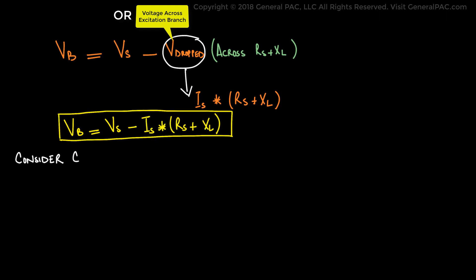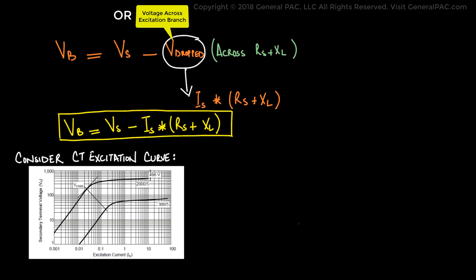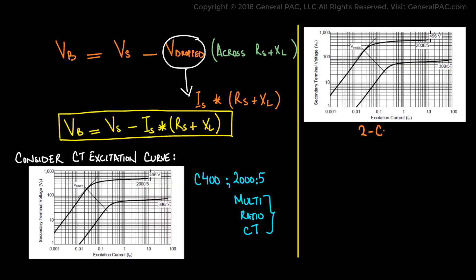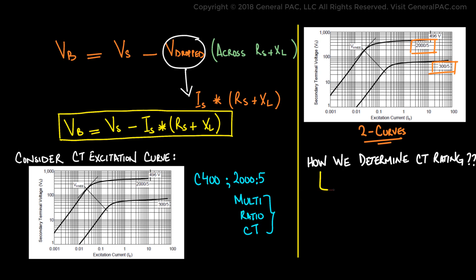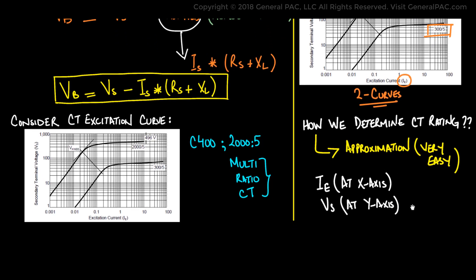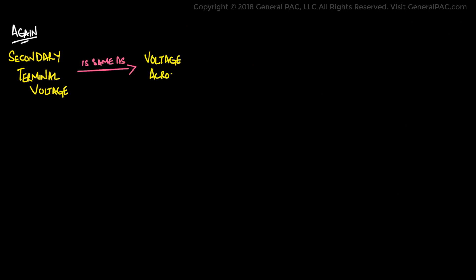Now let's consider an example of a CT excitation curve. The excitation curve shown here is for a C400 2000-to-5 multi-ratio current transformer. We see that it's multi-ratio because there are two curves — one representing 2000-to-5 and another representing 300-to-5. To determine the CT rating, we look at the excitation current on the x-axis and the secondary terminal voltage Vs on the y-axis. The secondary terminal voltage is the same thing as the voltage across the burden, which is a really important parameter.